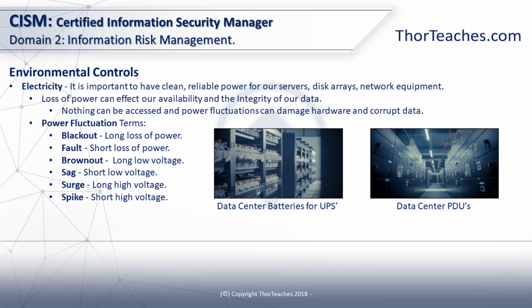Even if we have power issues in our area, it shouldn't affect our data center because our PDUs, our UPSs, and our generators will ensure that we have constant clean power at any time. A surge is high voltage over a longer period of time, and a spike is a short high voltage. Our servers, they'll never know the difference because we have all the countermeasures in place that ensure the clean, uninterrupted power. So let's take a look at how a power setup would normally function.